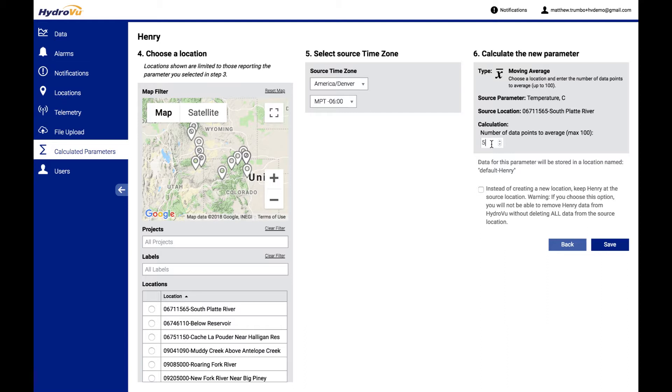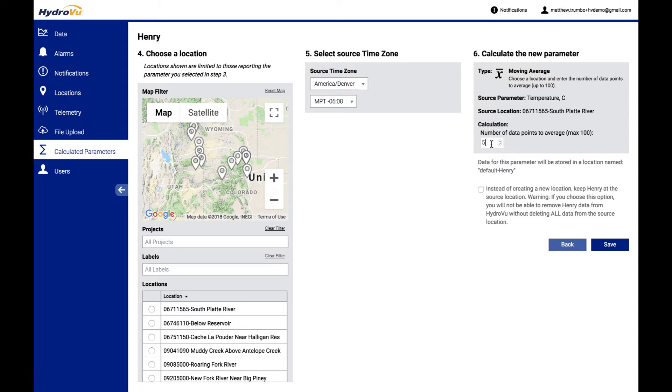That's a notoriously spiky measurement that can be very transient in terms of the conditions in the water. Something floats right in front of your sensor right when you take a measurement, you get a big spike. So if you had a mission-critical kind of alarm that you wanted to do, this would be a great way of making sure that it triggers only when you had a consistent change in your data.